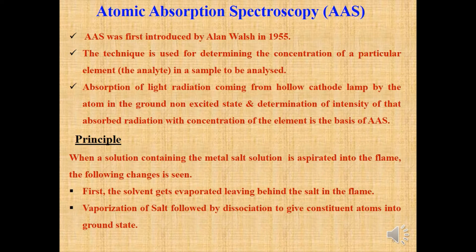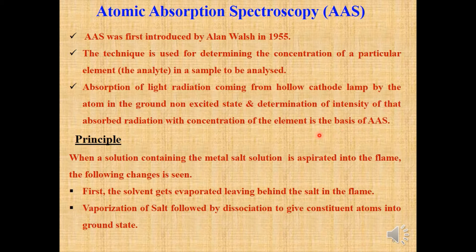Atomic absorption spectroscopy, also known as AAS, was first introduced by Alan Walsh in 1955. The technique is used to determine the concentration of a particular element present in the sample to be analyzed. Absorption of light radiation coming from the hollow cathode lamp by the atom in the ground non-excited state, and determination of the intensity of that absorbed radiation with the concentration of the element, is the basis of atomic absorption spectroscopy.